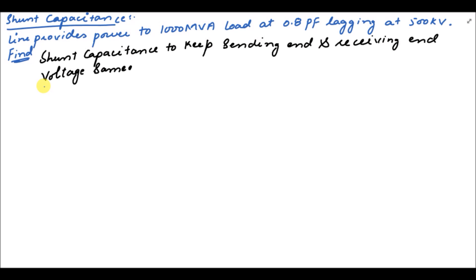Asalaamu alaikum. In today's lecture we are going to talk about the shunt capacitance addition at the end of the line in parallel with the load, whenever we have a voltage drop across the transmission line. In order to explain the shunt capacitance calculation, we are going to solve an example. In that example we have a load whose value is 1000 MVA at 0.8 power factor lagging.